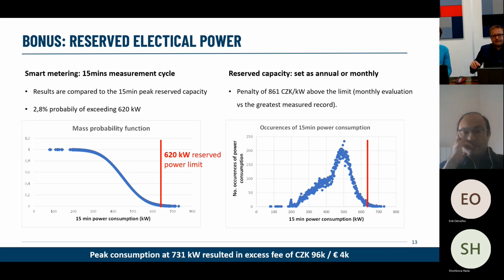Exactly. And these guys have set the reserved power limit at 620 kilowatts. So I've asked the maintenance manager to send me an annual record that can be downloaded from the electrical meter. And as you can see, there were occurrences on the right-hand side when they exceeded the 620 kilowatts reserved power limit. If you exceed that reserved power limit, you have to pay 4 times more per kilowatt than you would below that limit.